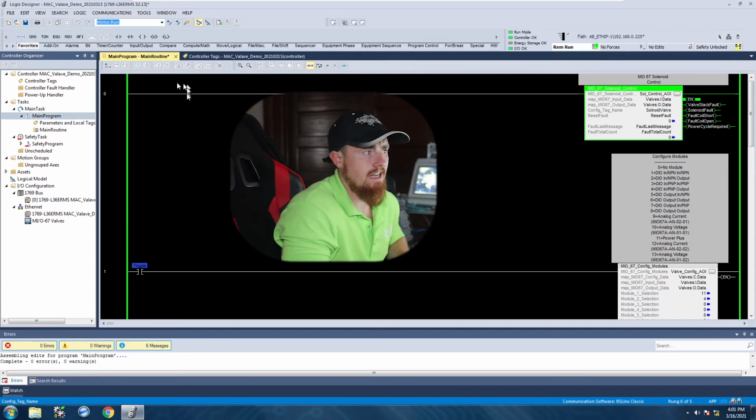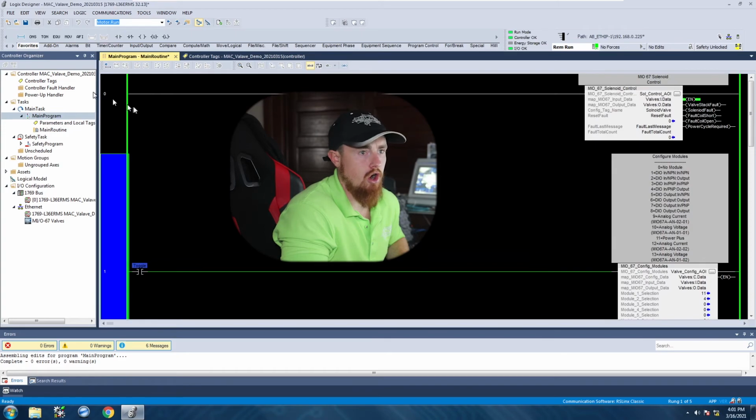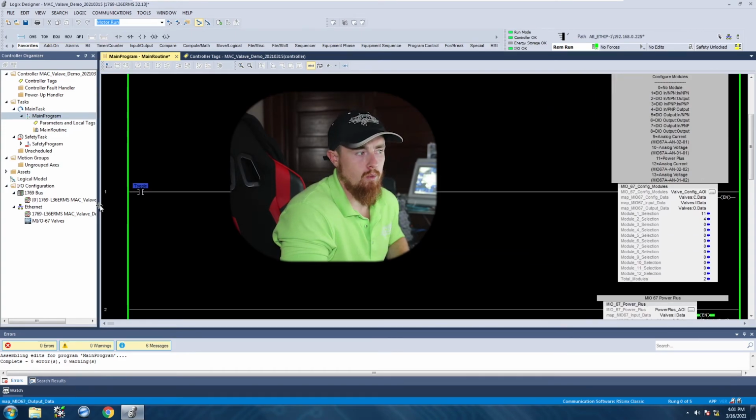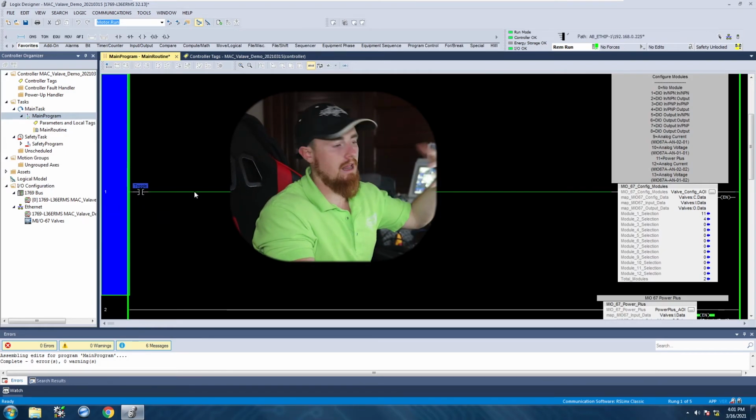Part of this could be the fact that we have these AOIs online before we push the configuration. So it's essentially already trying to write to these AOIs constantly, yet we haven't even told it what it's going to be yet. And since they don't know what it's going to be, you're trying to write to something that may not even be there yet.